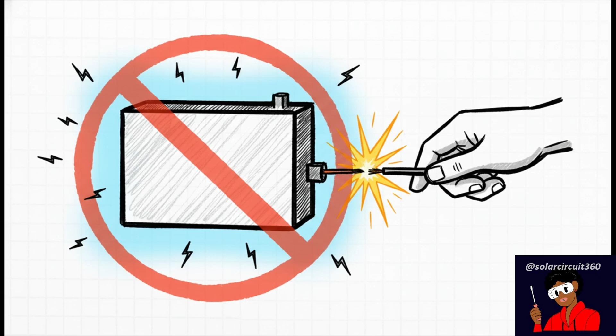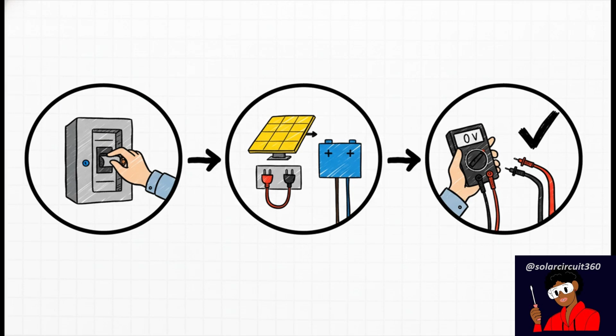This is precisely why you never work on a system when it's live. That leads us to this non-negotiable, written-in-stone rule: never, ever try to connect new parts, panels, batteries, anything, while the system is powered on. A sudden voltage mismatch can cause a huge surge of current, meaning sparks, potential arc flashes, and fried components. So before you even think about touching a wire, kill the power.